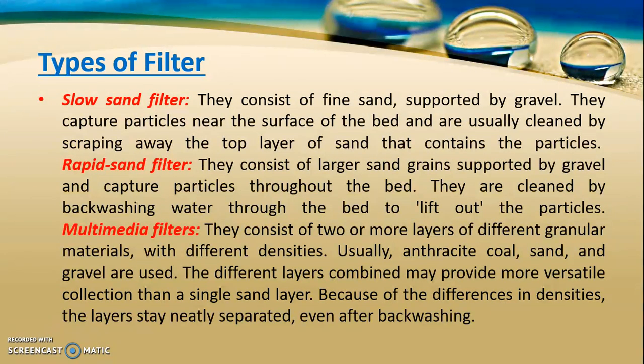There are different types of filters. The most common types are slow sand filter, rapid sand filter, and multimedia filter. Slow sand filters consist of fine sand supported by gravel — gravel at the bottom and sand at the top. They capture particles near the surface of the bed and are usually cleaned by scraping away the top layer of sand that contains the particles. Rapid sand filters consist of larger sand grains supported by gravel and capture particles throughout the bed.